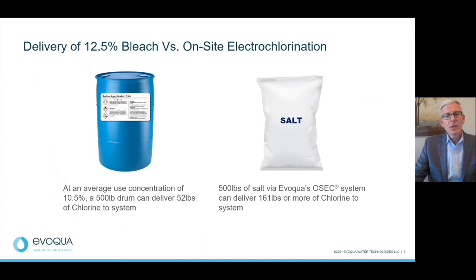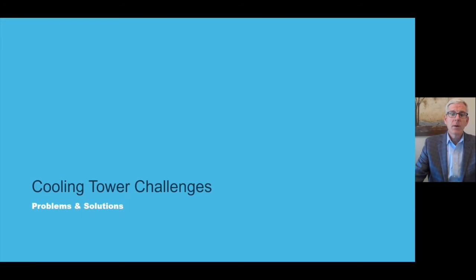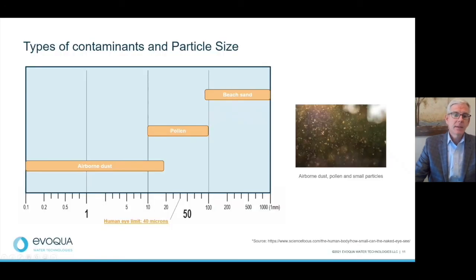So now that we've established the relationship of the specialty chemicals used to the carbon impact on your supply chain, let's see how we can further reduce the chemical demand of your cooling system. Now, one of the characteristics of the cooling tower is that it allows airborne particulate to enter the water. This can be dust, pollen, or even insects. These particles become suspended in the water, and the amount of particles in the water is often measured and reported as total suspended solids, or TSS. Suspended solids put a demand on your water treatment chemistry and can lead to you feeding more chemistry than you need. This is because TSS can promote the growth of bacteria and can deposit out in the system, leading to fouling and corrosion issues.